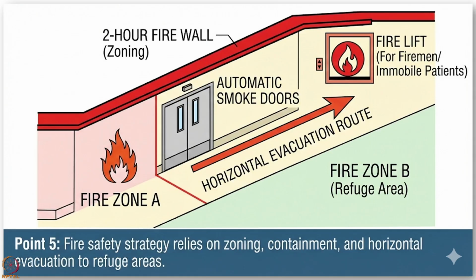Now, in this particular figure, you can see the fire safety strategies, which rely on zoning, containment and horizontal evacuation to refuge areas. You may find a fire happening over here, and you may come across a horizontal evacuation route, where a 2-hour firewall zoning is insulated, and a fire lift for firemen and immobile patients, with proper signages, and a fire zone area called a refuge area, which is to be emphasized more in the design. This figure highlights the importance of fire safety strategies.